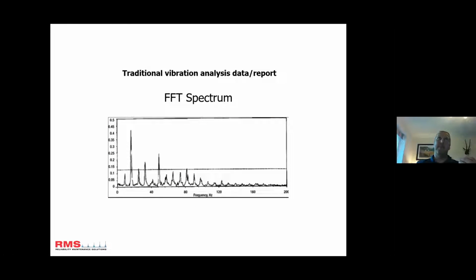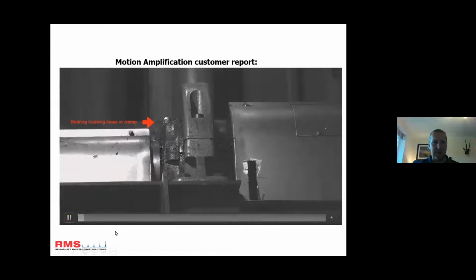I'd say the biggest benefit of the technology is as a communication tool between engineers, because not everyone is a vibration analysis expert or CBM guy. Someone doing vibration might look at this spectrum graph with the peaks and say, if that first peak's running speed, that might be looseness. But to a lot of people, it doesn't mean anything. If I show you a video of that same problem, suddenly we look at it, it's the Cooper bearing, maybe some looseness between the D clamp and the cartridge on the inner. It's a lot easier to understand, and this is one of the most powerful things about the technology.